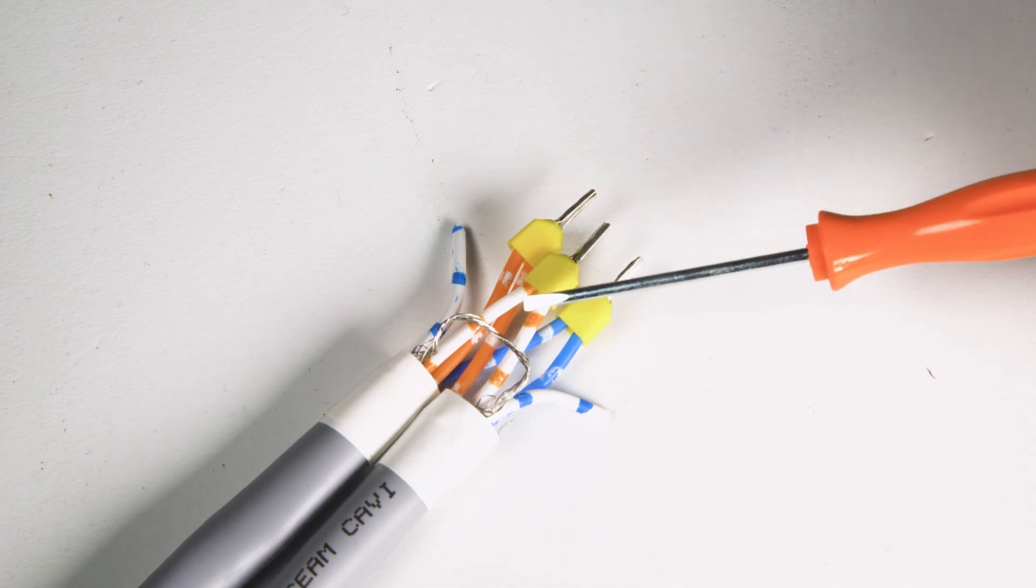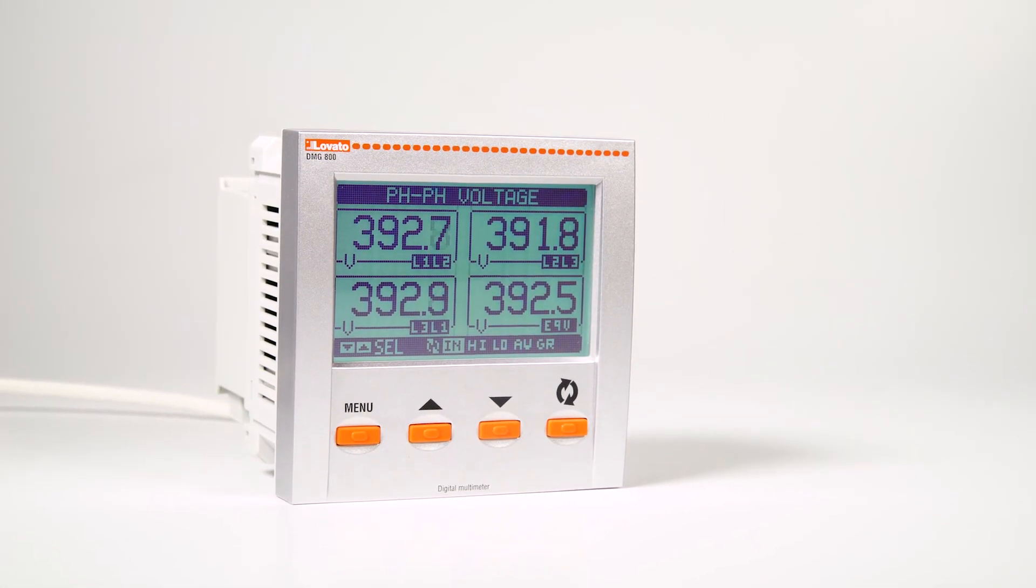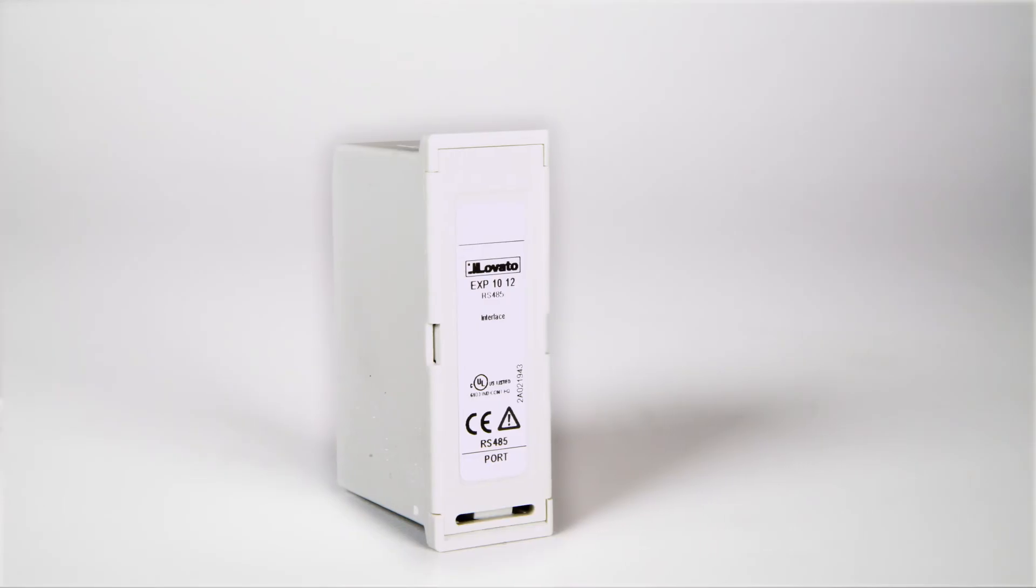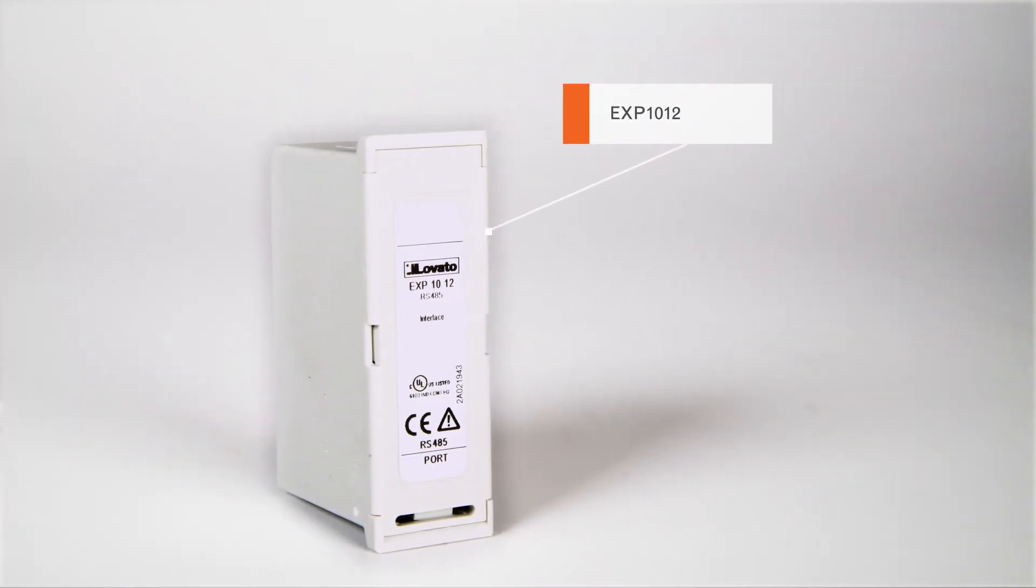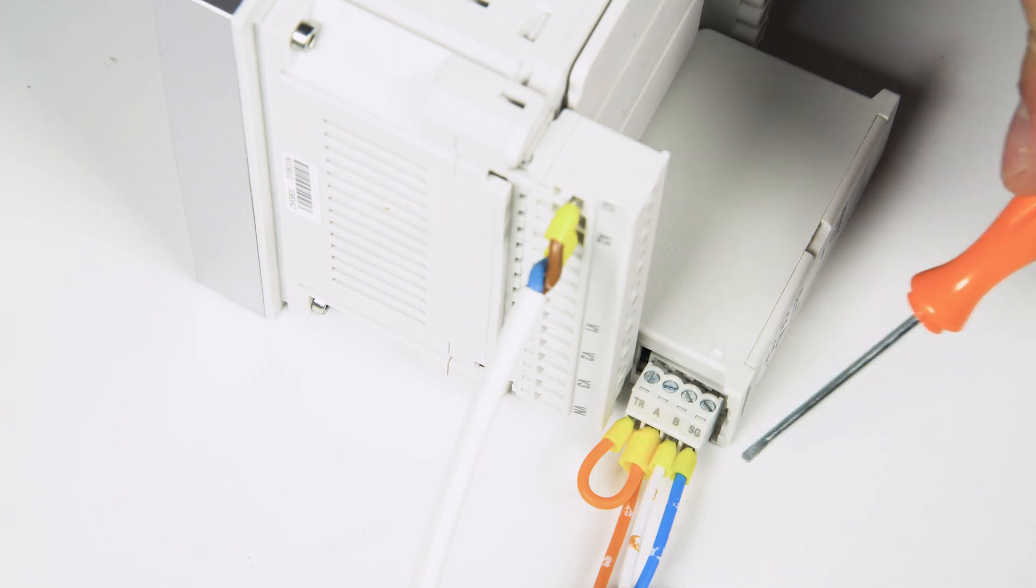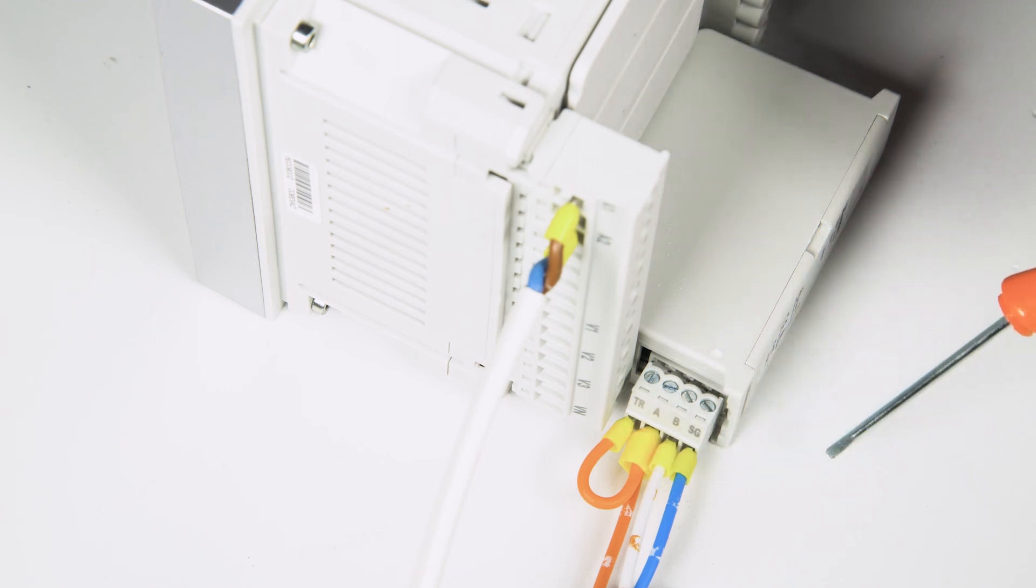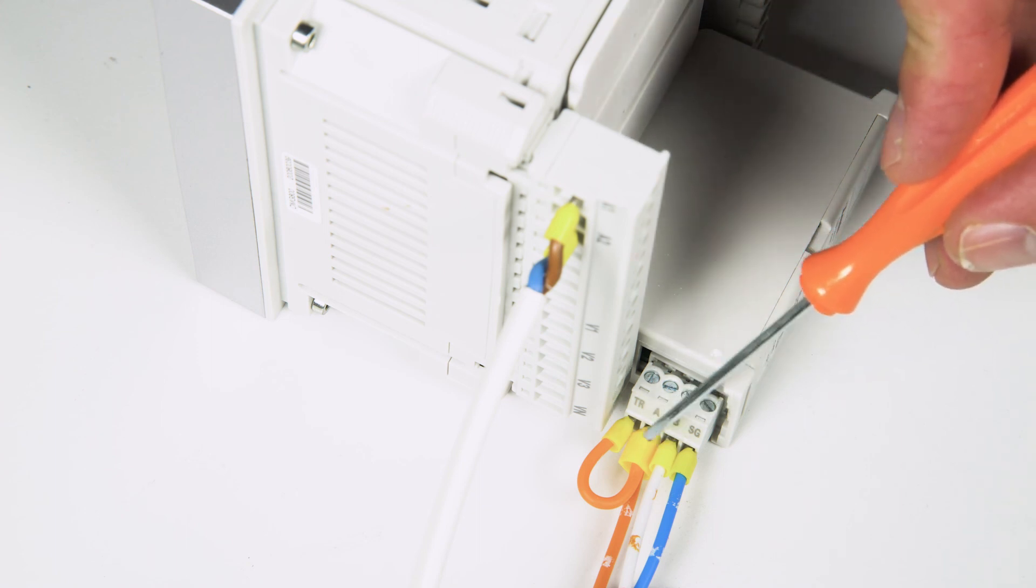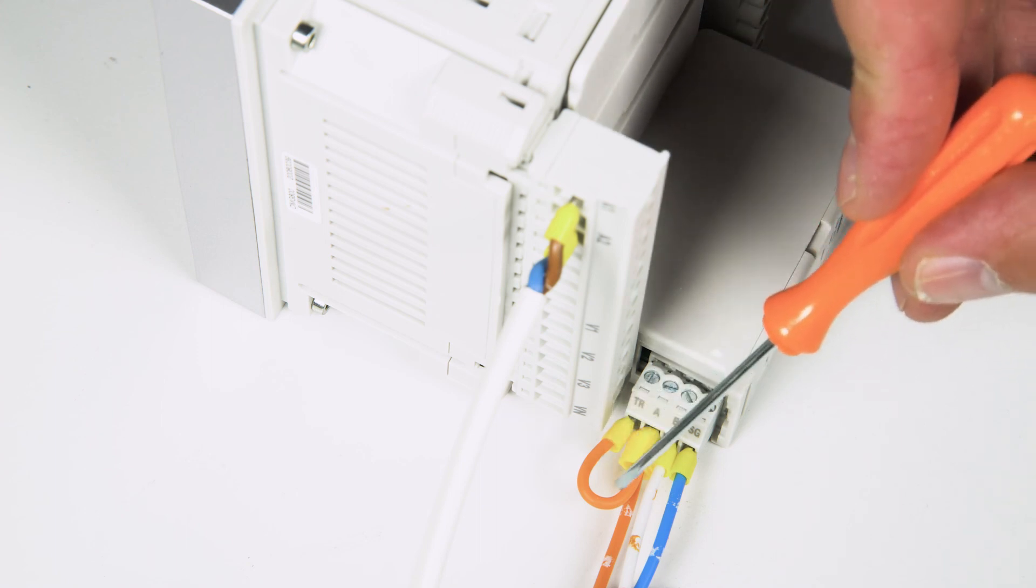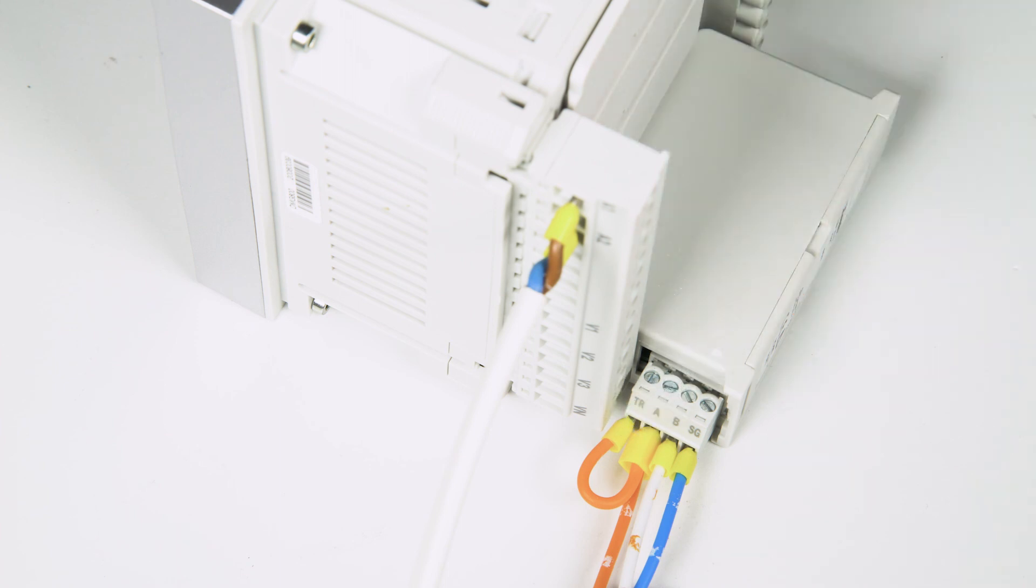The last instrument connected in this sample network is a panel mount DMG-800 with an EXP-1012 expansion for communication via RS-485. Connect cables A, B and the reference negative in single mode as usual. Since it is the last instrument in the network, bridge terminal A and terminal TR to correctly terminate the measuring network.